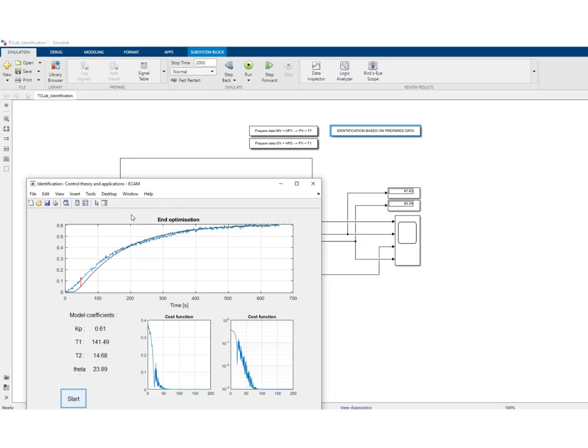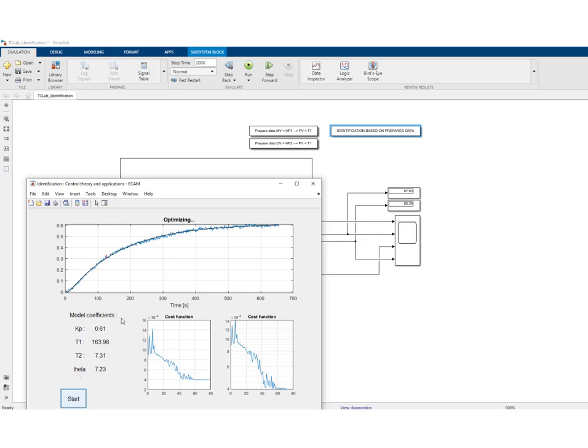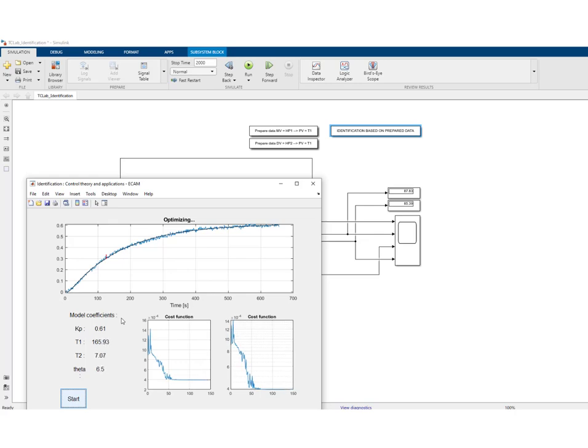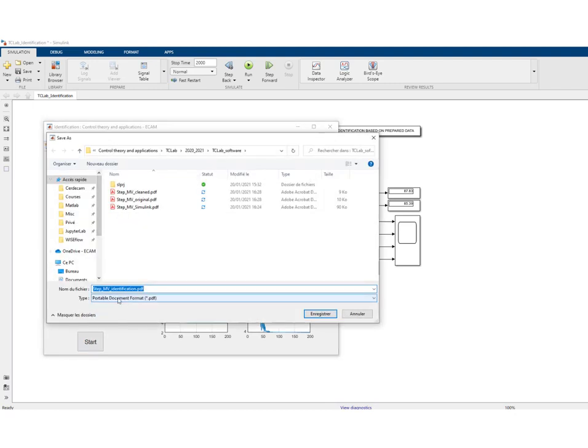We have reached the end of the optimization but are not completely satisfied. We'll run the optimization again starting from the current parameters. Now it's starting to improve, and we are going to be satisfied — this is a very good fit. This is the identified gain of the Van der Grinten model — a model with two lag time constants, a gain, and a delay.